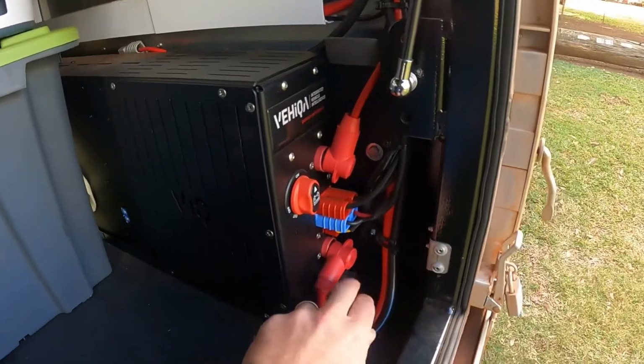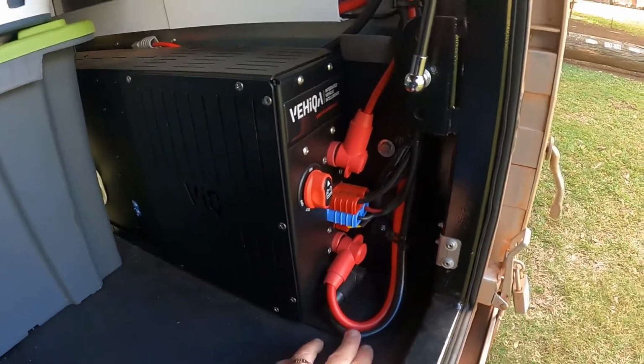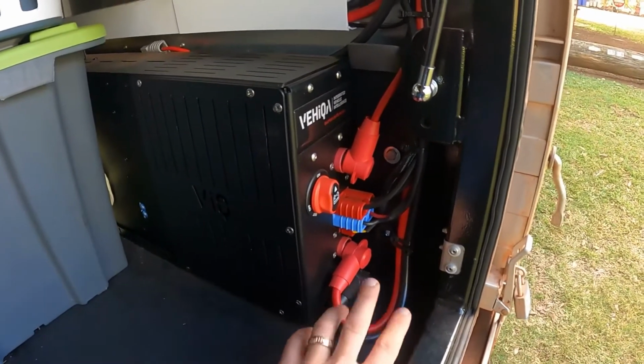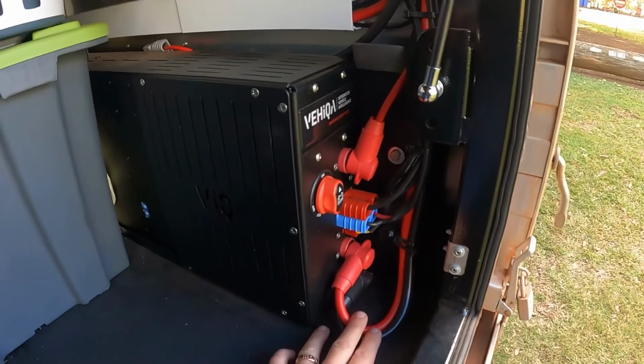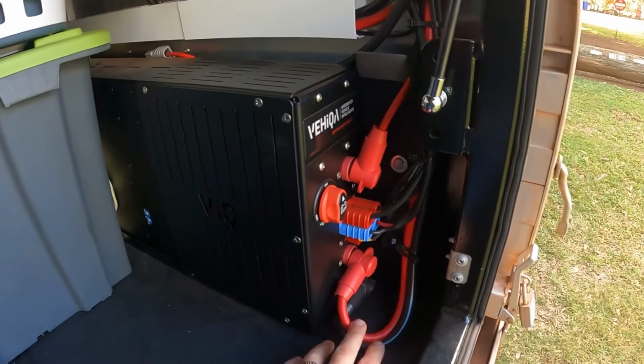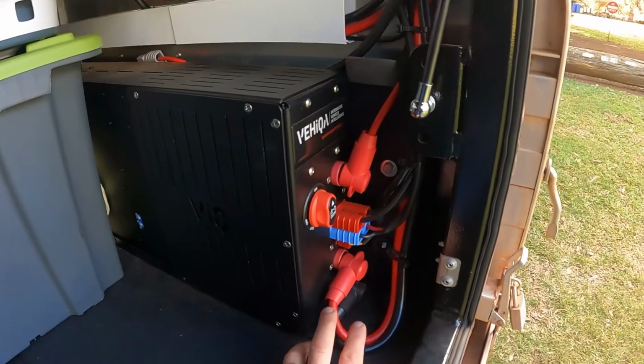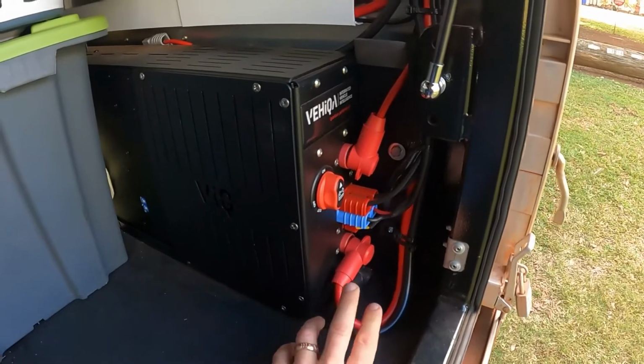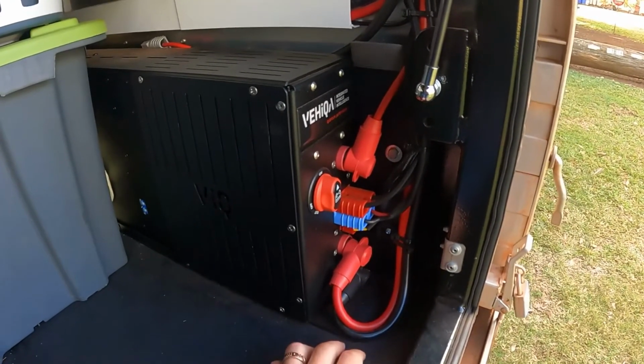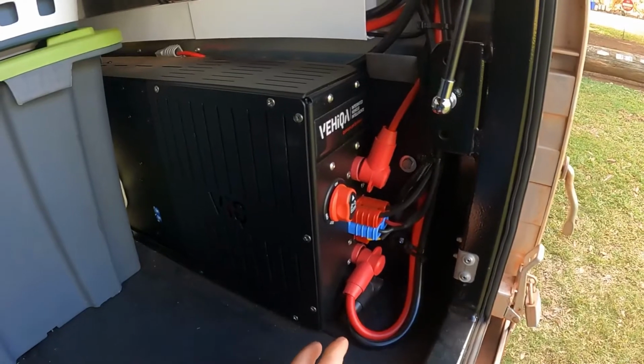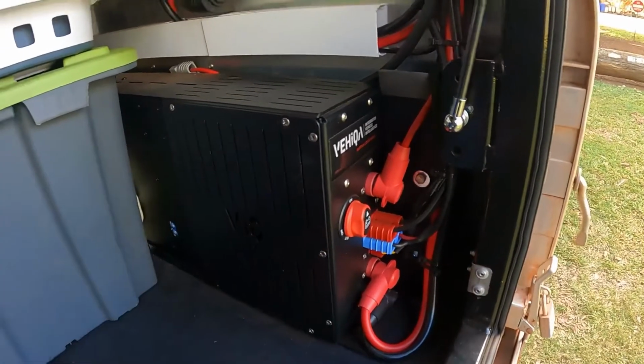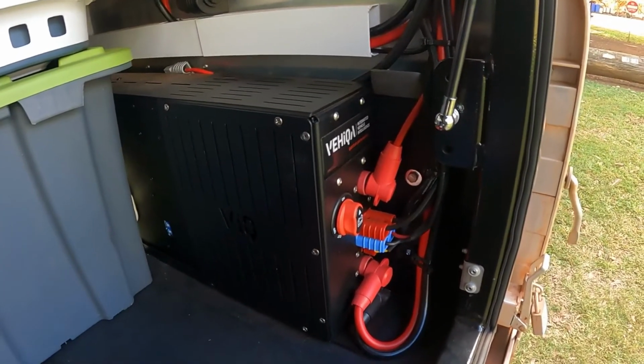The two studs down the bottom here are your inverter and your main earth, so they're not protected by low voltage disconnect, only from the battery management system inside the battery, but most inverters these days also have a low voltage disconnect. The other good thing is these batteries have their own resettable circuit breakers built inside.